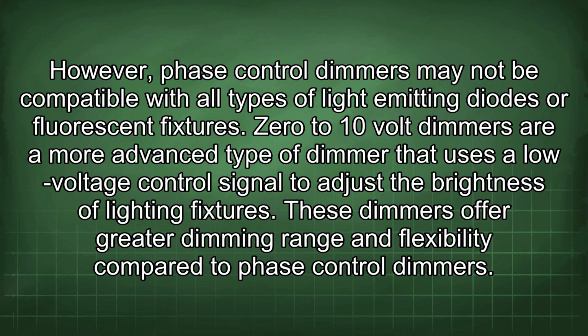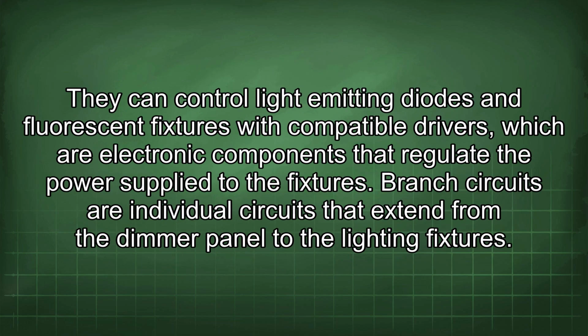0 to 10 volt dimmers are a more advanced type of dimmer that uses a low-voltage control signal to adjust the brightness of lighting fixtures. These dimmers offer greater dimming range and flexibility compared to phase-control dimmers.